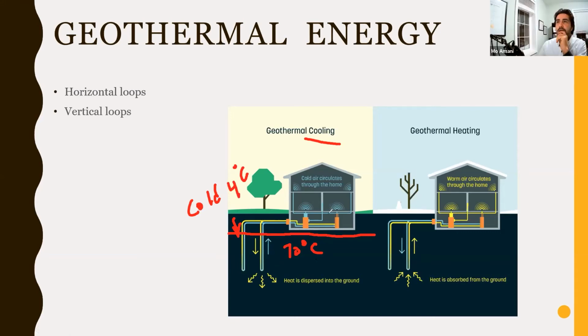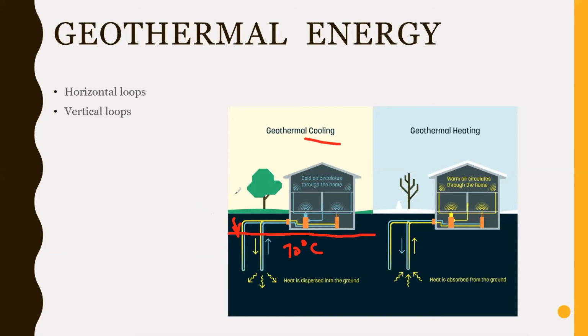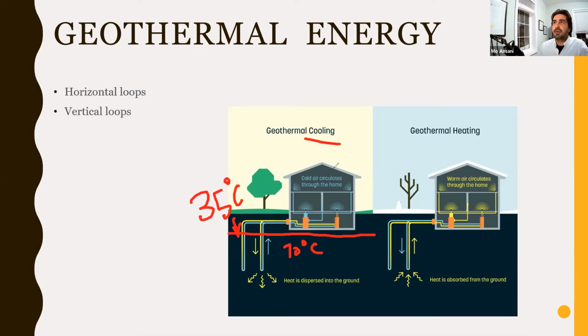If I may correct: when you're in cooling mode, you're actually sending water at around 35 degrees Celsius, because you're taking heat from the house and sending it to the pipe, and that temperature could be 35, even 40 degrees Celsius. On the heating side, when you do heating, you extract at an average of around 30 degrees and use it to heat the house.